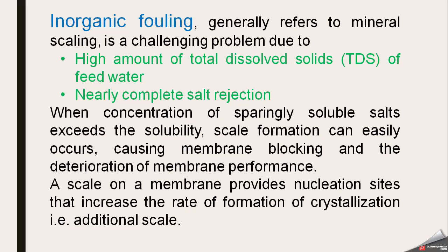What happens in this process? Very importantly, when the concentration of sparingly soluble salts exceeds the solubility, these salts start precipitating upon reaching their solubility product limit, scale formation starts and it can easily occur.